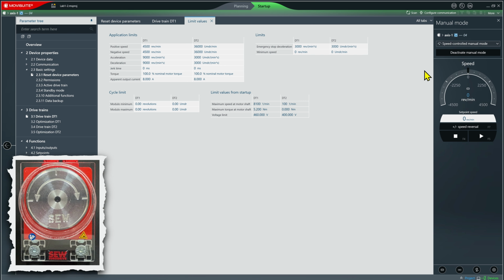So I'm going to do that by clicking the play button here. And I hear a click as my brake releases, and I'm going to start the motor spinning. And you can see there we go, we're spinning away. You check the other direction. Runs in both directions just fine. Notice I can do a few other things. I have a speed reversal button. I can click this to go back and forth.